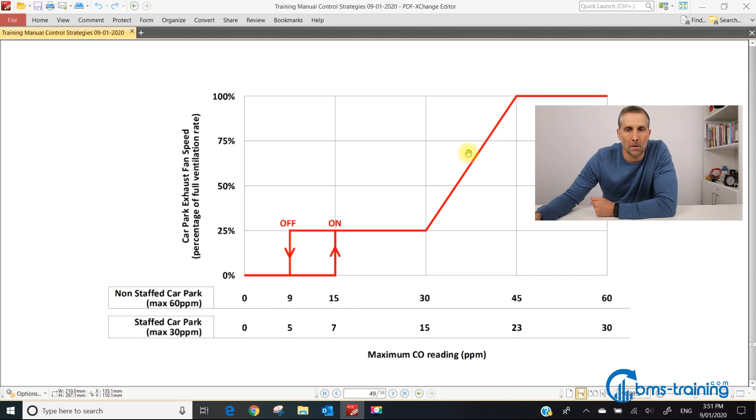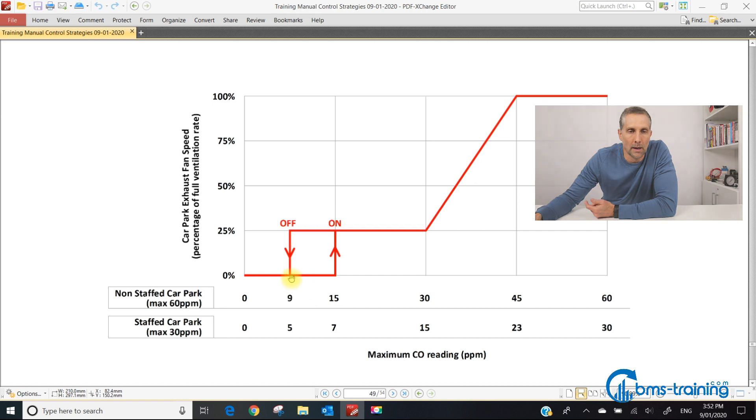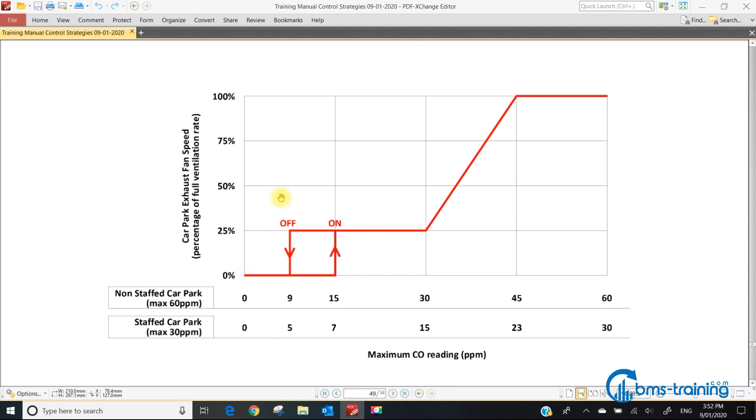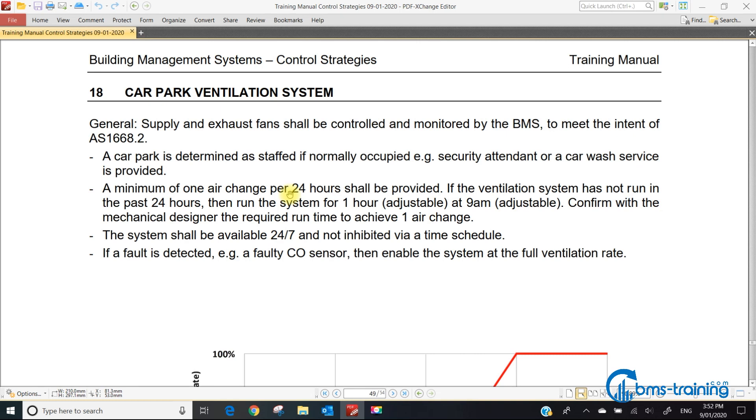The fan turns off when it goes below 9 parts per million. When the fan's not running, a minimum of one air change per 24 hours shall be provided. Confirm with the mechanical engineer the required runtime. As BMS people we don't know what an air change is, so just put a time schedule that runs the plant for one hour if it hasn't run for 24 hours.